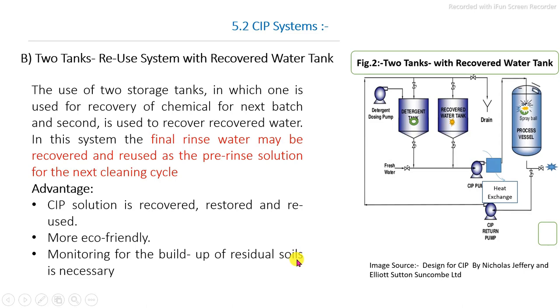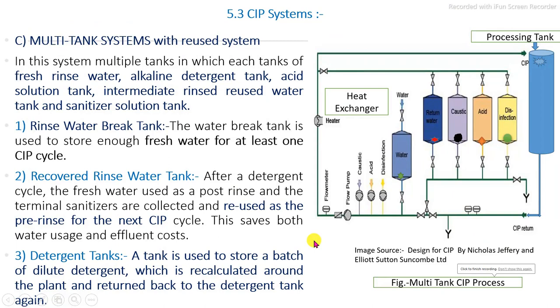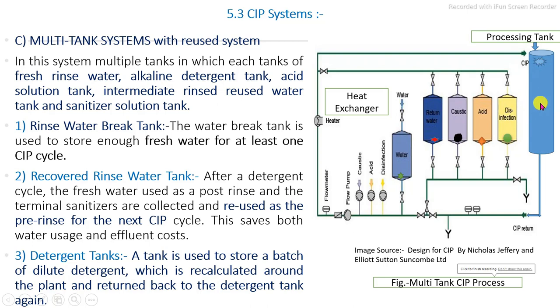The third option is the multi-tank system with a reusable system. Multi-tank means more than two tanks, including a fresh water tank, return water tank, caustic solution tank, acid solution tank, and disinfectant solution tank. This is the complete multi-tank CIP system, connected with the processing vessel or processing line, with a recycling system in which all detergents, waters, and disinfectants are separately stored and reused for the next batch.